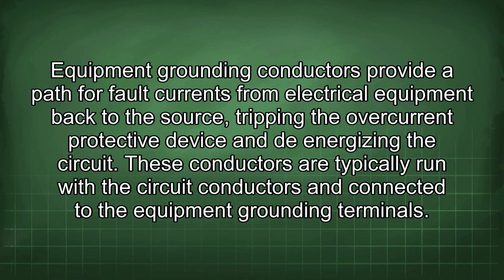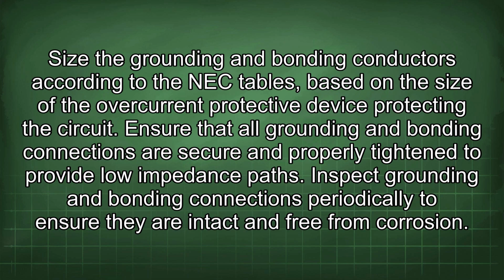Equipment grounding conductors provide a path for fault currents from electrical equipment back to the source, tripping the overcurrent protective device and de-energizing the circuit. These conductors are typically run with the circuit conductors and connected to the equipment grounding terminals. Size the grounding and bonding conductors according to the NEC tables based on the size of the overcurrent protective device protecting the circuit. Ensure that all grounding and bonding connections are secure and properly tightened to provide low impedance paths.